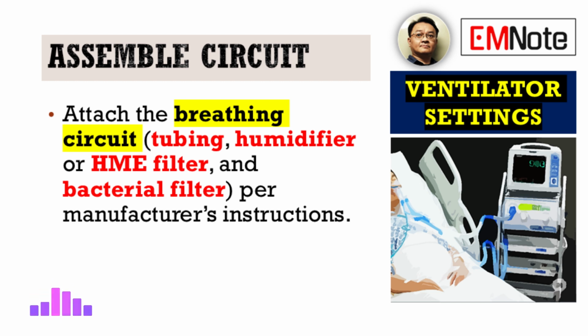It typically includes the main ventilator tubing that carries the inspiratory and expiratory gases. It also includes either a humidifier or what's called a heat and moisture exchanger filter. These condition the air, add warmth and moisture. Proper humidification is vital. It prevents drying and damage to the patient's airways, and additionally, an inline bacterial filter is often included. This prevents microorganisms passing into or out of the circuit.